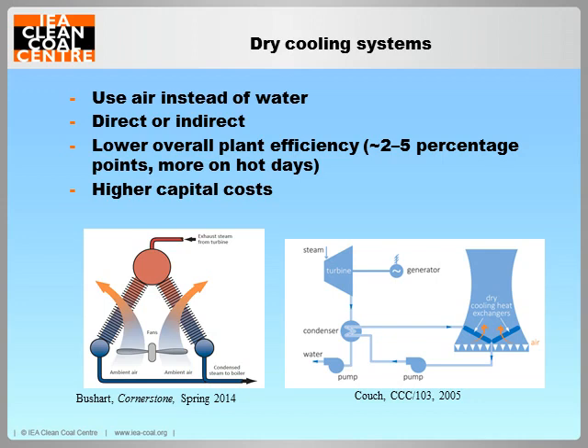Right, substantial water savings could be made by employing dry cooling, which utilises air instead of water to condense the steam. For example, one power plant in South Africa that employs a direct dry cooling system uses about 3.5 million cubic metres of water per year. And this compares to around 50 million cubic metres per year for an equivalent wet-cooled power plant. So this is saving over 46 million cubic metres a year, or if you prefer, 46 billion litres of water a year.